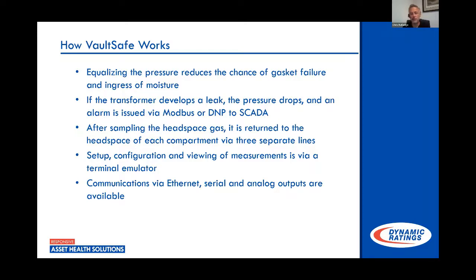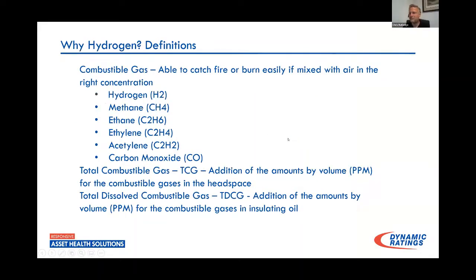So communications out of this unit, we can go out via Ethernet or serial. There are some analog outputs as well. And then for protocols, it's available in DNP and Modbus. So combustible gas, we've talked a lot about hydrogen. You do get your alarm. So what do I do then? Well, again, the first thing to do is let's get this transformer out of service, and let's find out where our problem is. So we're getting our alarm in the gas space.